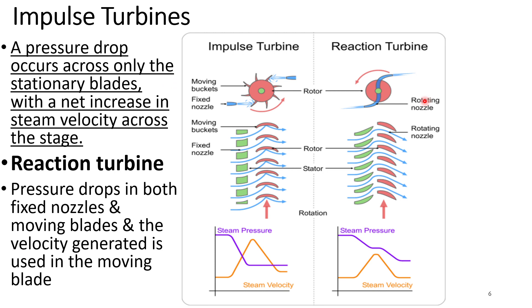There are basically two types of turbines: impulse turbine and reaction turbine. In an impulse turbine, pressure drop occurs only in the stationary blade with a net increase in steam velocity across the stage. In a reaction stage, pressure drops in both the fixed nozzle and the moving blade, and the velocity generated is used in the moving blade.